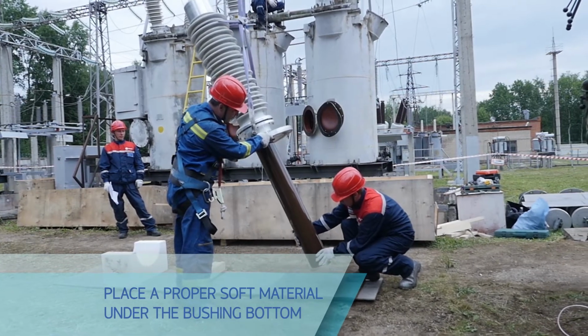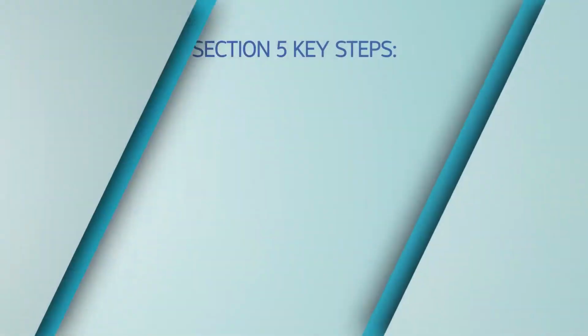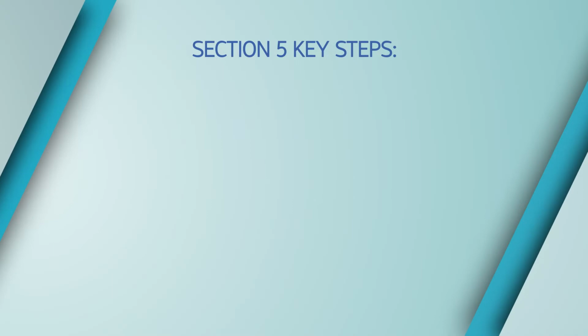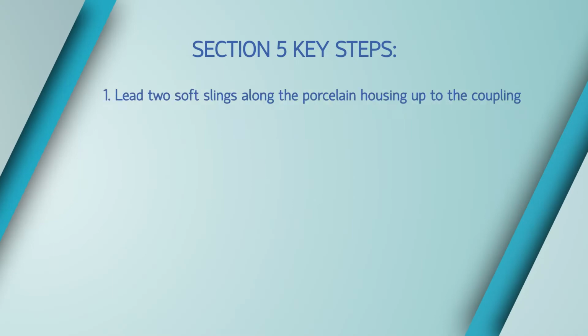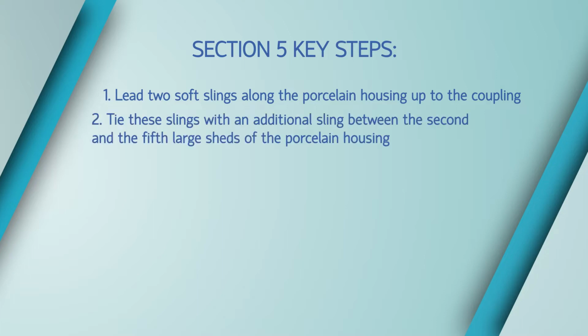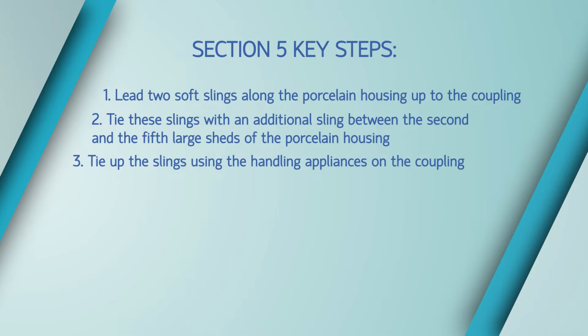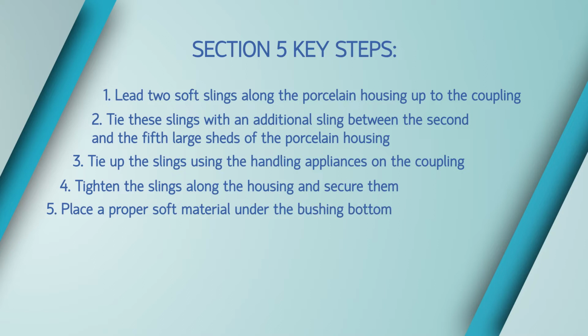We have just seen how to set the bushing vertically on a stand. Let us go through the key steps again. Lead 2 soft slings along the porcelain housing up to the coupling. Tie these slings with an additional sling between the 2nd and 5th large sheds of the porcelain housing. Tie up the slings using the handling appliances on the coupling. Tighten the slings along the housing and secure them. Place a proper soft material under the bushing bottom. Set the bushing vertically on a process stand.